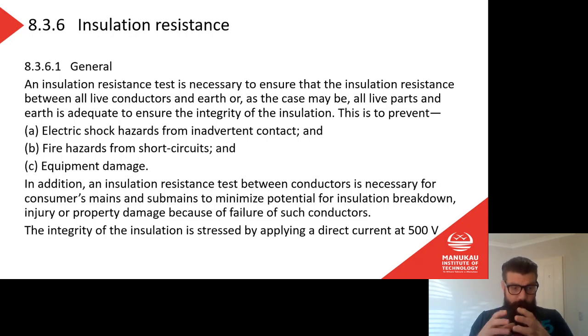And with insulation resistance, it's exactly the same thing. If I have poor insulation, the higher the voltage is, the more chance that it's going to jump out of that hole to somewhere that it's not supposed to be, like to me or somebody else. And also when we get that really high voltage, it could start to break down the insulation itself. That's where it makes the hole bigger in the pipe with the bigger pressure. So we're going to test with a higher voltage than we are ever going to see on that circuit to make sure that it's good. If it operates okay when we test it at 500, then it certainly should operate at 230 volts. Hopefully that makes sense.